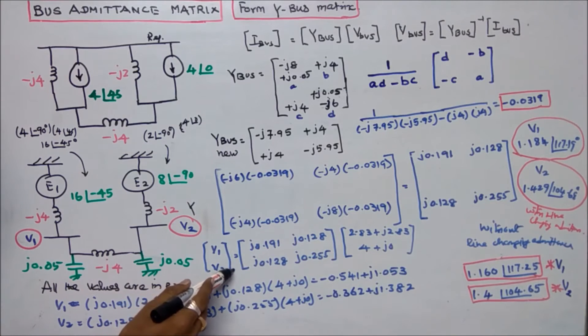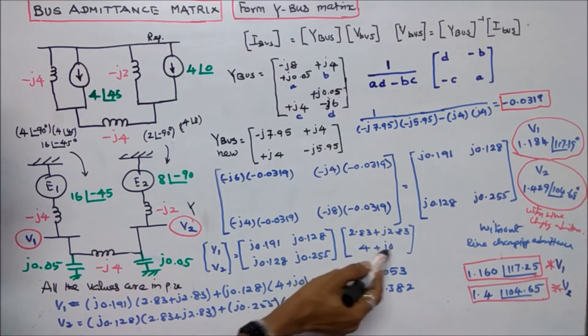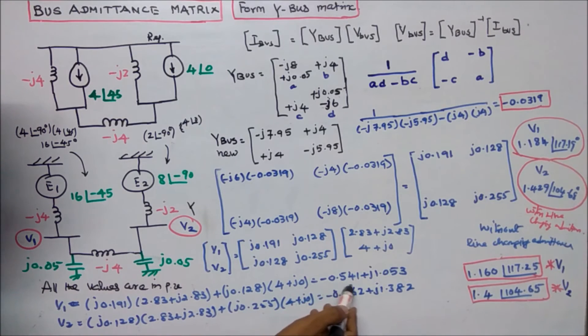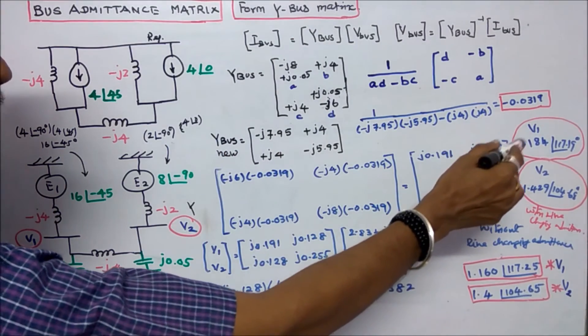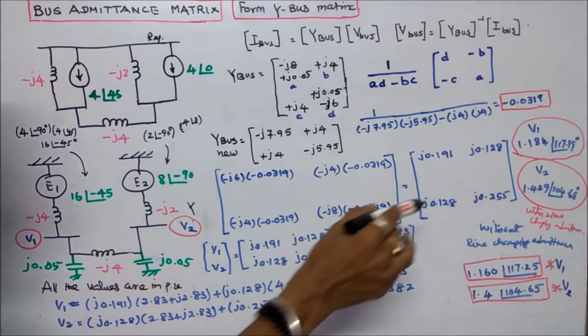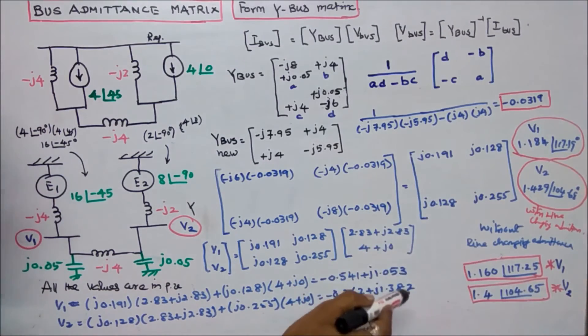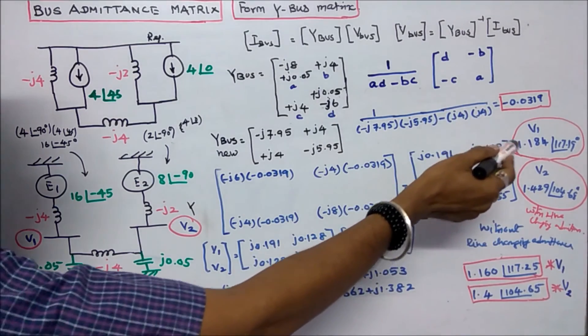Computing V1 and V2: V-bus equals Y-bus inverse matrix times [2.83 plus J2.83; 4 plus J0]. V1 in rectangular form equals minus 0.541 plus J1.053. In polar form, V1 equals 1.184 angle (approximately). Without line charging admittance, V1 was 1.160; with line charging admittance, V1 is slightly increased to 1.184.